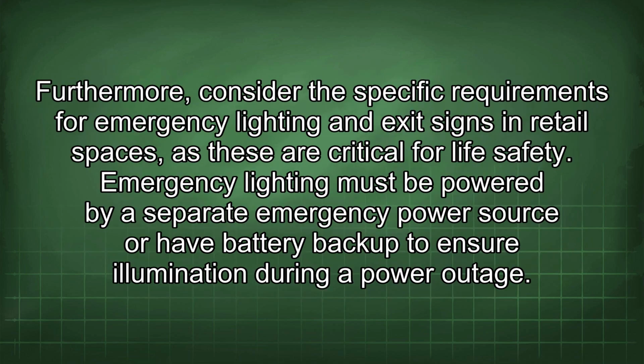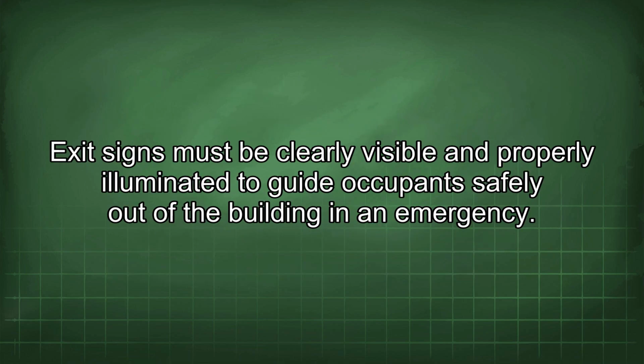Furthermore, consider the specific requirements for emergency lighting and exit signs in retail spaces, as these are critical for life safety. Emergency lighting must be powered by a separate emergency power source or have battery backup to ensure illumination during a power outage. Exit signs must be clearly visible and properly illuminated to guide occupants safely out of the building in an emergency.